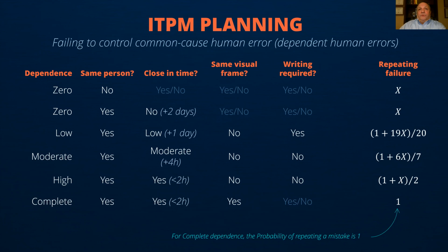So it's better to stagger maintenance between inspection of redundant channels. The staggering could be either 3 days between them by the same person, or have a different person do the inspection test check on the same day.